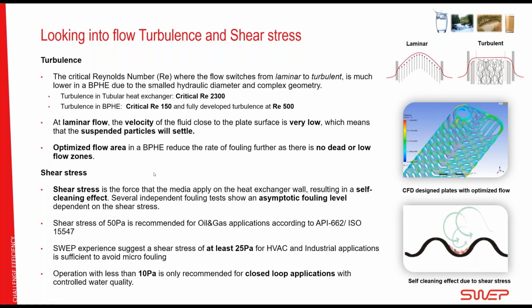Let's move over to shear stress. Shear stress is the cousin of turbulence, the strong cousin, I would say. So shear stress is the force that the fluid applies on the heat exchanger wall, which is what we call the self-cleaning effect. So a high shear stress is able to clean away dirt that is starting to settle.